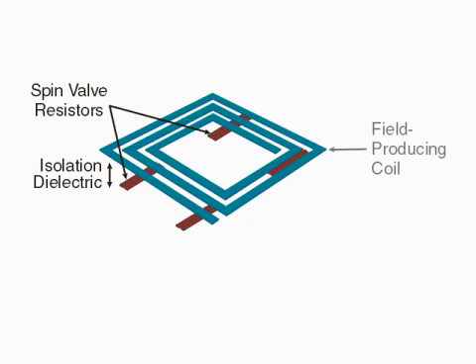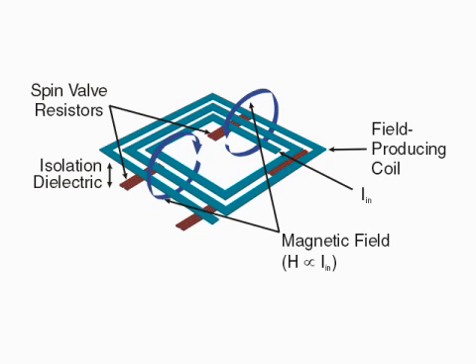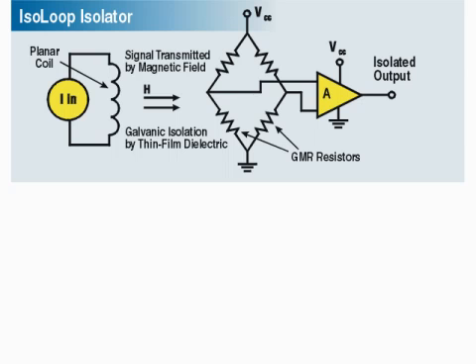The coil creates a magnetic field proportional to the input current. The field changes the spin polarization of the spin valves, which changes their resistance. The output is amplified and conditioned to produce an isolated replica of the input.